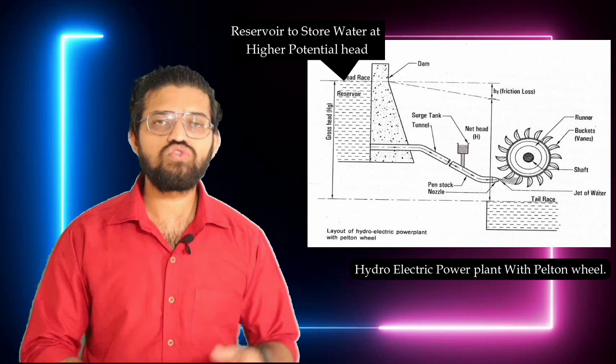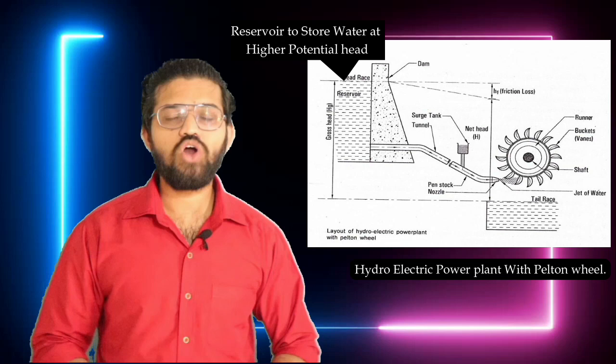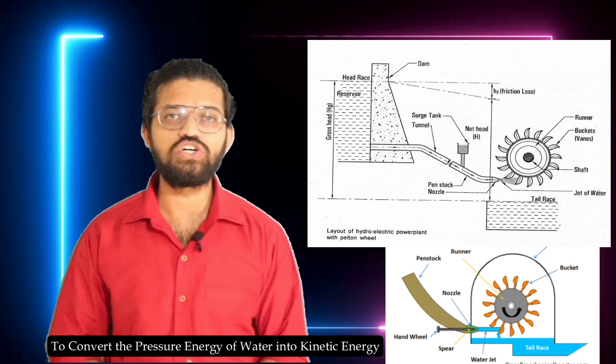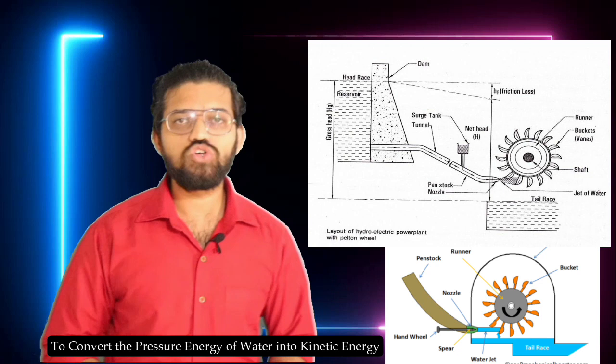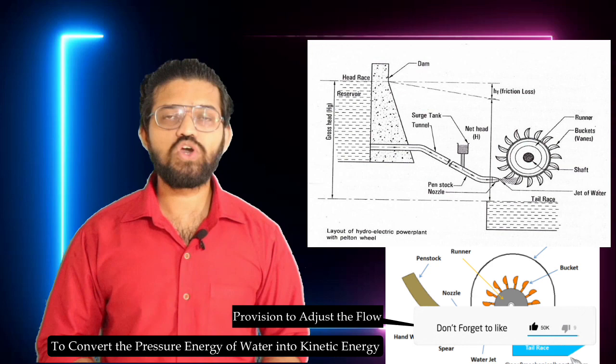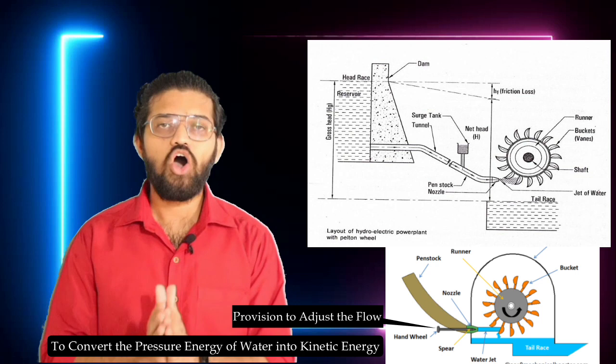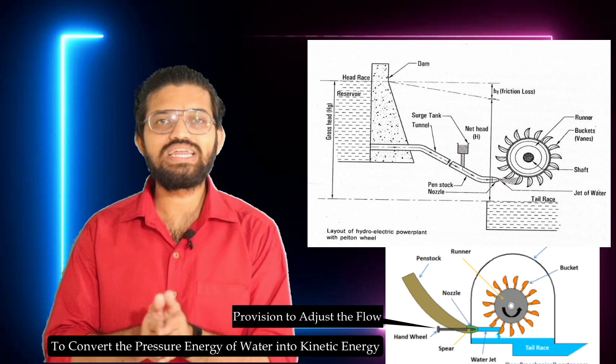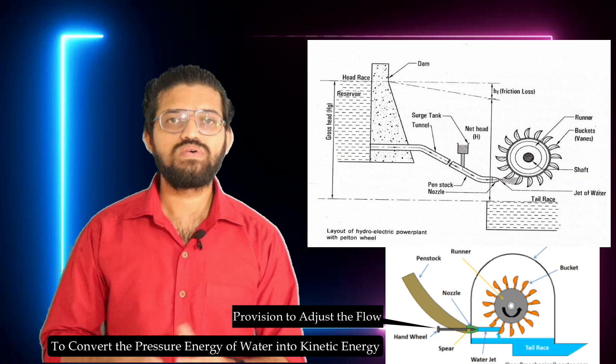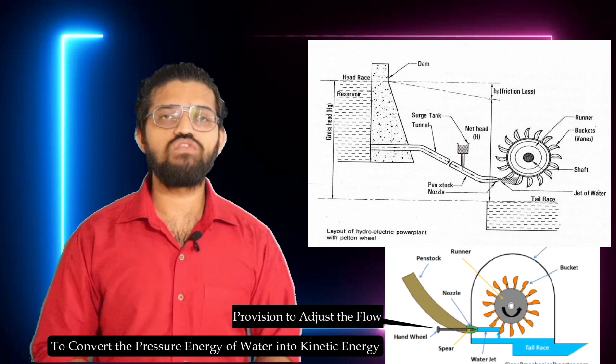This water is allowed to flow through the penstock, and at the end of the penstock there is a nozzle. The main function of the nozzle is to convert the pressure energy of the water into kinetic energy, increasing the velocity of the water. The nozzle also has a screw assembly that allows us to increase or decrease the discharge — that is, the flow rate — through the nozzle.